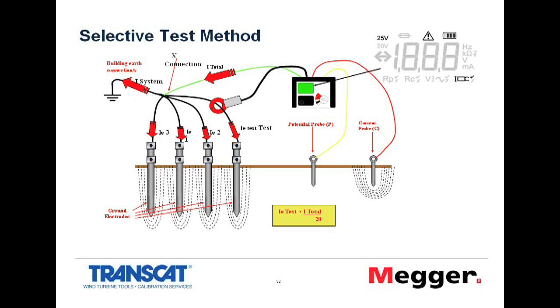The selective test method is more practical for the substation end of things. Here we have a 3-pole tester, and the challenge is that I've got multiple electrodes to ground, and I need to measure one electrode.